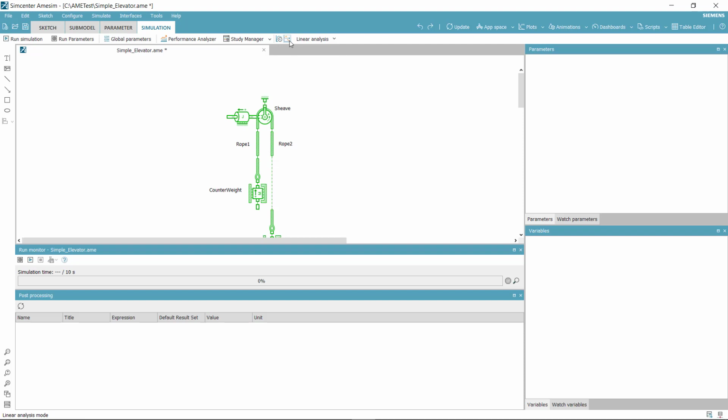Linear analysis mode. With the linear analysis, the dynamic behavior of the system is studied through the eigenvalues of the system, representing the system nature modes. They allow the prediction of the possible resonances of the system occurring at specific frequencies, as well as the associated damping ratio of the oscillation. The mode shapes, representing the space distribution for nature mode all along the system.